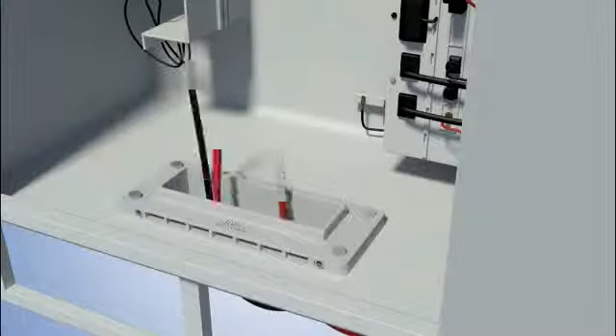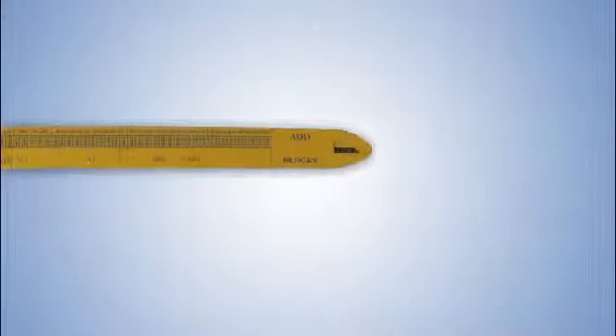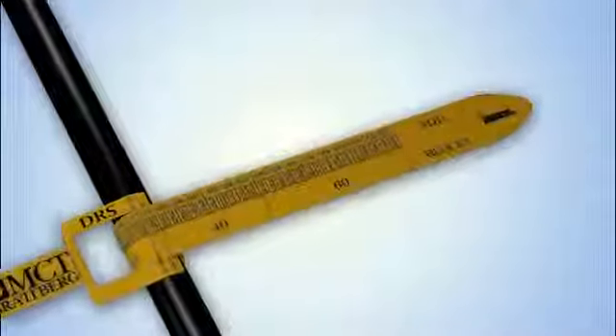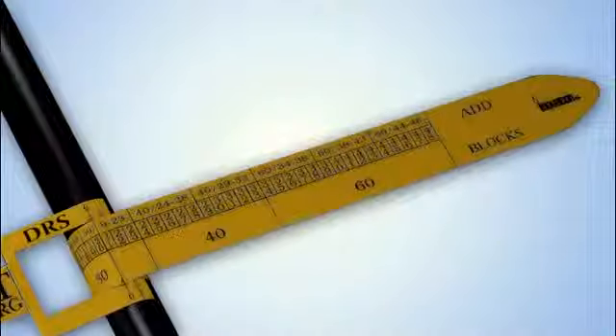Now use the cable selector to measure the exact diameter of the cable. Wrap the cable selector around the circumference of the cable and read off the diameter of cable to select the correct module.